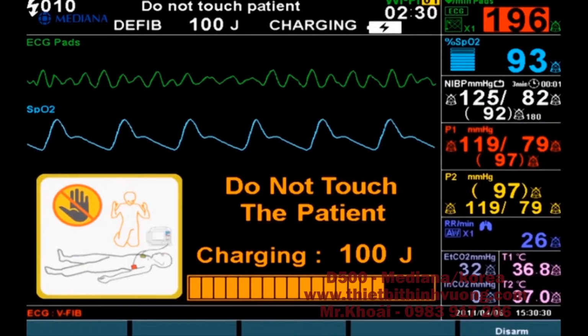We can perform AED operation following the guide with action icons and voice prompt, and actually, this guideline complies with the AHA 2010 guideline, the recommended CPR guideline from American Heart Association. These 7 steps are what you will see to follow when performing the AED mode. After verifying if the AED mode is activated, these action icons will be displayed step by step with the matched audible guidance that you can see right next to each action icon. All you have to do is just follow these steps.